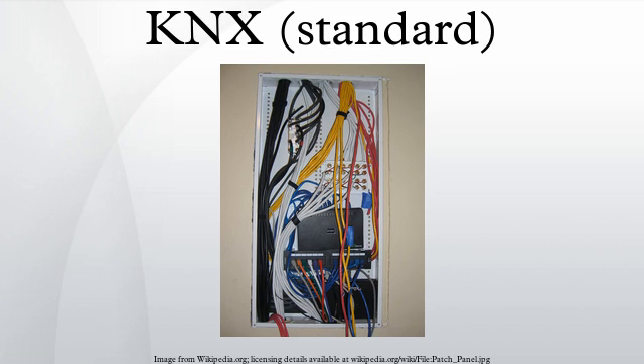There are three categories of KNX device. A-mode or automatic mode devices automatically configure themselves and are intended to be sold to and installed by the end user. E-mode or easy mode devices require basic training to install; their behavior is pre-programmed but has configuration parameters that need to be tailored to the user's requirements. S-mode or system mode devices are used in the creation of custom building automation systems; they have no default behavior and must be programmed and installed by specialist technicians.